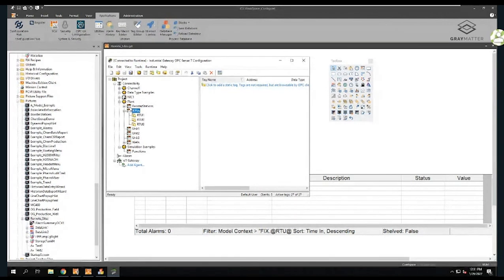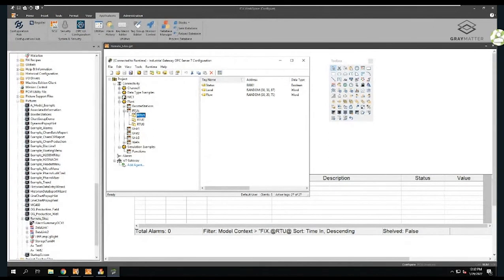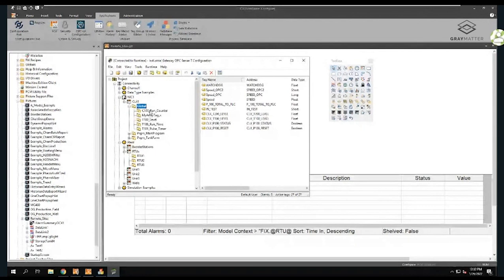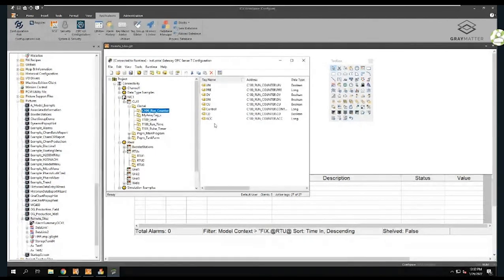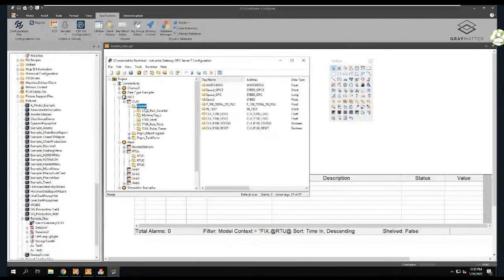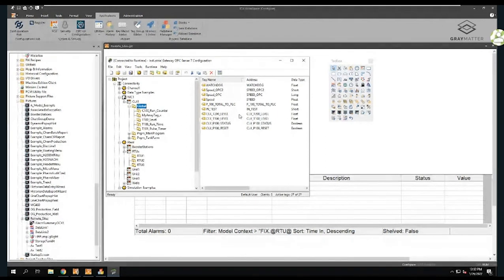On the topic of dynamic addressing: a lot of times we can read in the controller configuration using the IGS driver, depending on what controller you have. Popular Rockwell controllers and other symbolic controllers will build the structure up for you, and the goal is we can leverage that as well. Just because variables are here in the driver doesn't mean they're being requested - the driver is only going to request what's in the iFIX database. Even if you have a bunch of process variables you're not using, the driver is not going up to request that information.